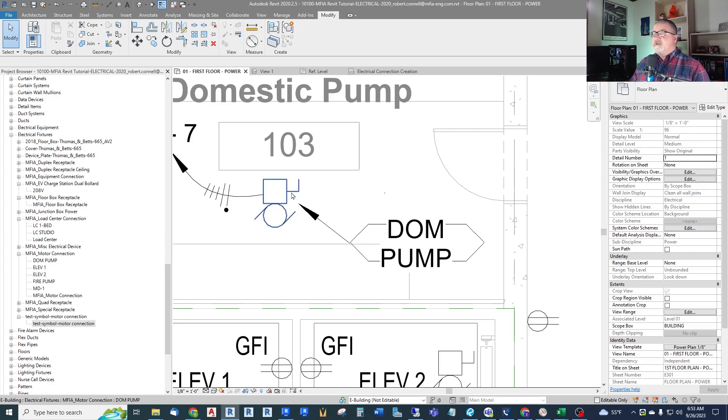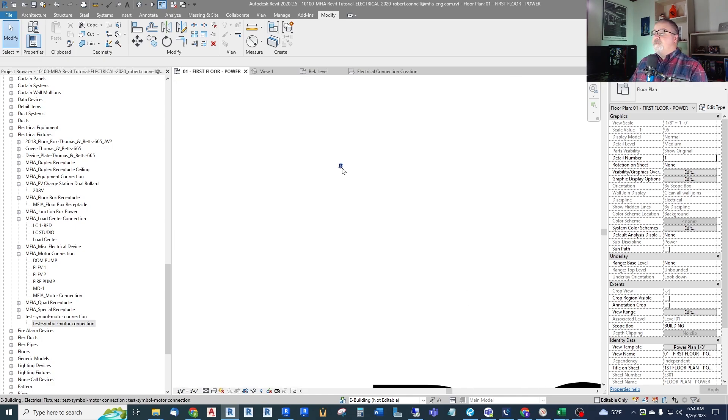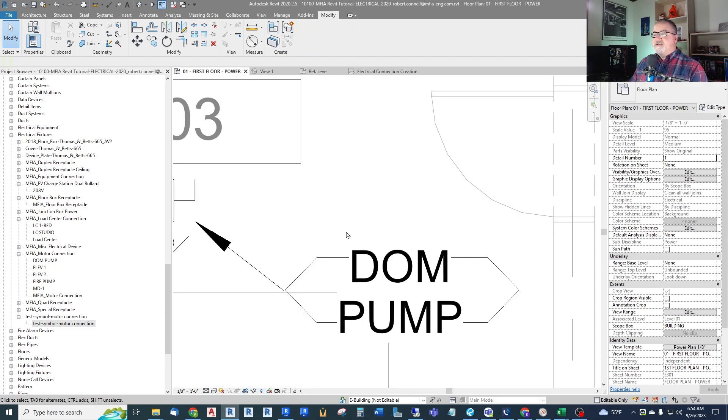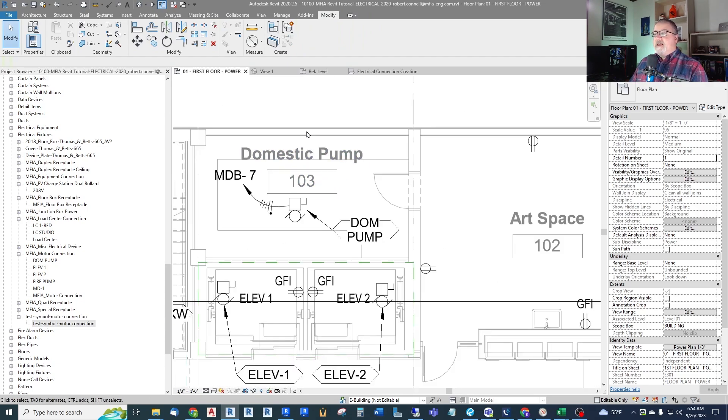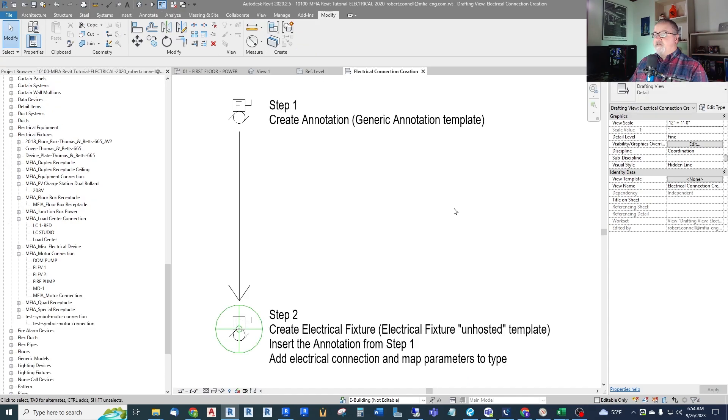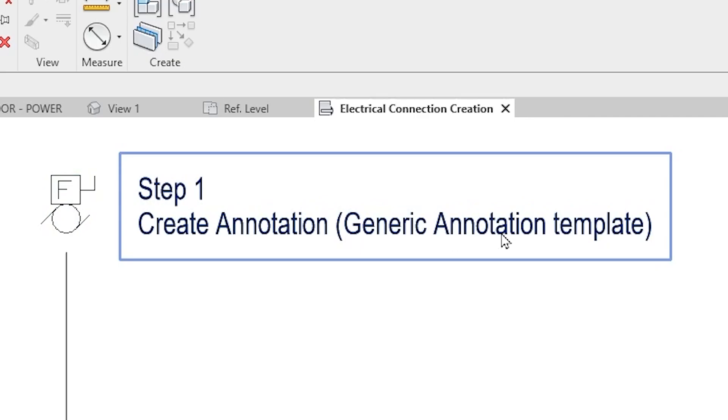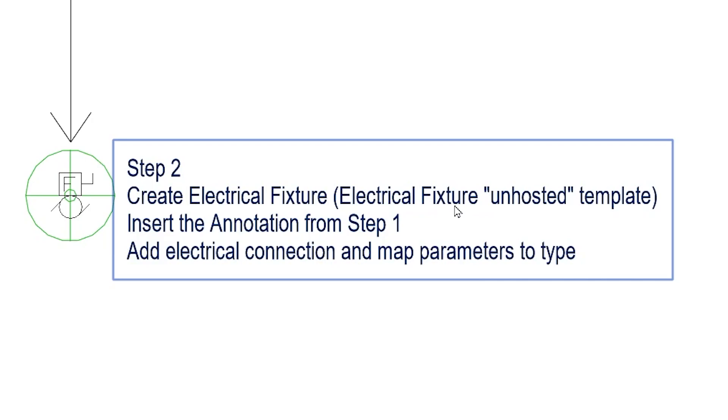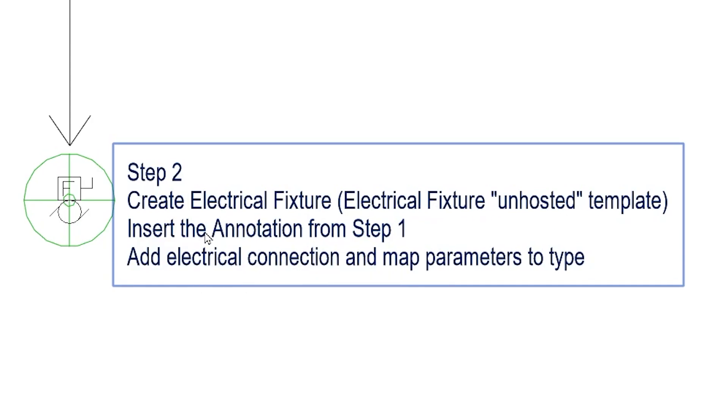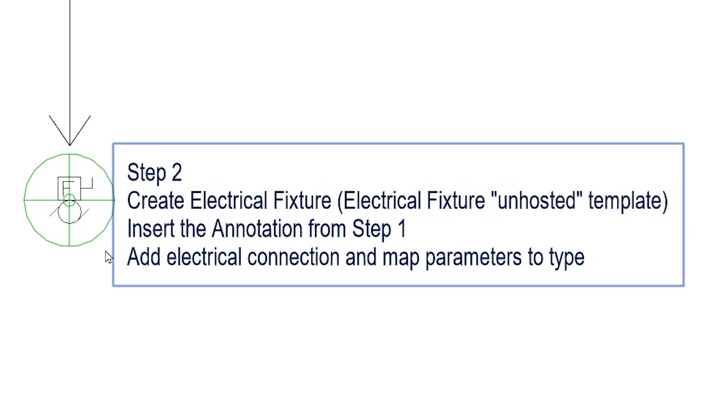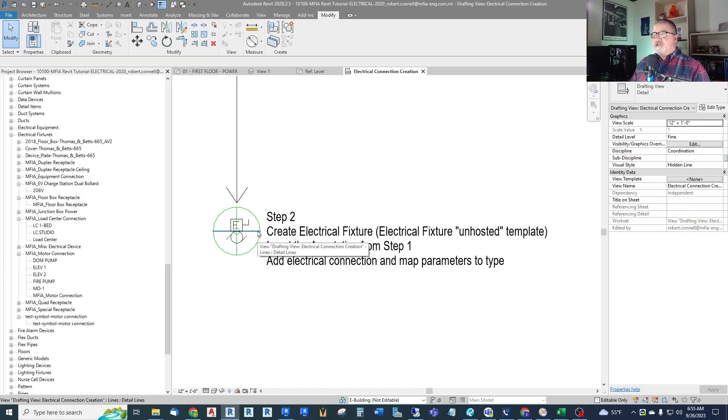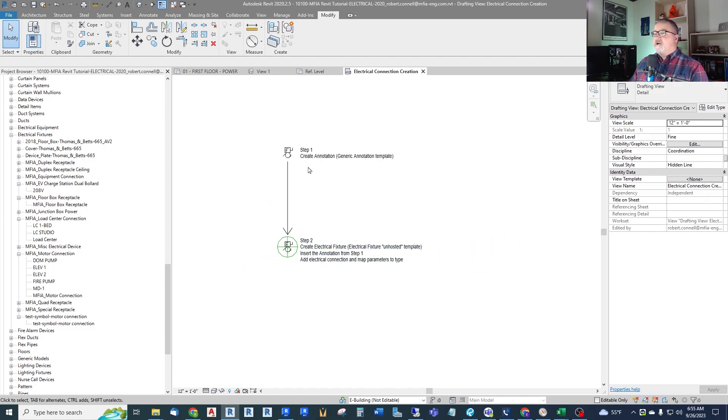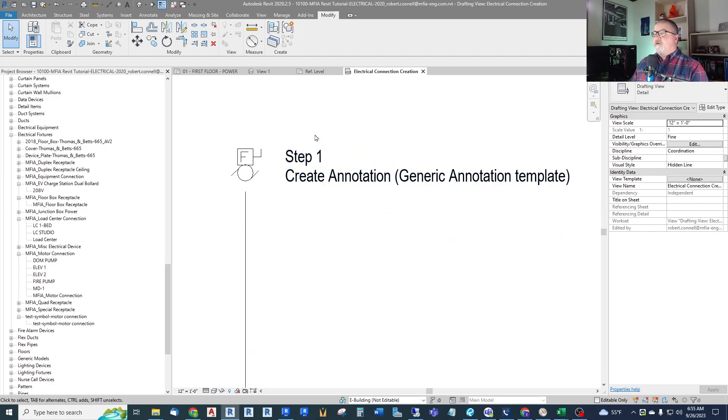So I need to create something that actually is the proper size and is always the same eighth inch circle type symbol. So the way we do that is we have to create the annotation symbol first as a generic annotation. And then we bring that into our electrical fixture. So I just have a view here, gave a simple chart here. Step one is we're going to create the annotation itself as a generic annotation from the template. And then we are going to create an electrical fixture using the electrical fixture template, an unhosted. We're going to insert the annotation from step one into this family. And then we will also add our electrical connection, the green circle, and map the parameters of that connection to our type so that we can get to those within our model. So let us start with step one, create this annotation.